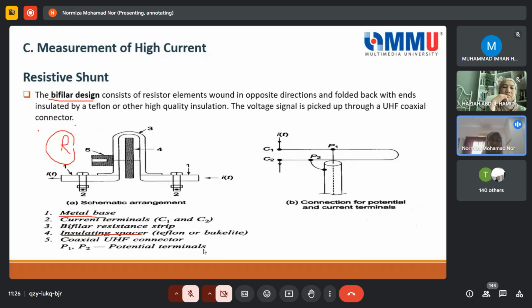You need it small because the voltage is 100 kilovolt applied on the test load, and you have to make sure that the 100 kilo amp, for example, is safely captured by the oscilloscope, whose maximum range in terms of voltage is 50 volt. So you have to make sure that the current from 100 kilo amp is very much reduced to below 50 volt, the level that can be captured by the oscilloscope.